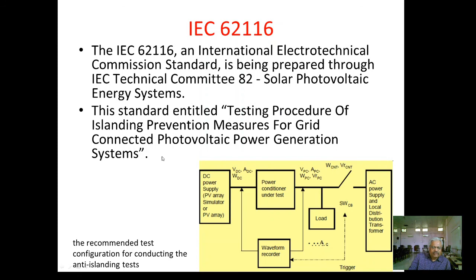Now, whether anti-islanding is important. There has been an argument that because the probability of islanding is extremely low, it may be a non-issue in practice. However, there are counter-arguments also. Firstly, the low probability of islanding is based on the assumption of 100% power matching between the DG and islanded load. In fact, an island can be easily formed even without 100% power matching. The power mismatch could be up to 30% if only traditional protections are used, e.g. under/over voltage and frequency. The 30% power mismatch condition will drastically increase the islanding probability.